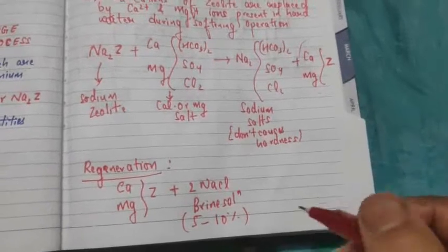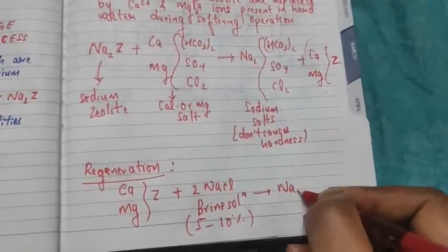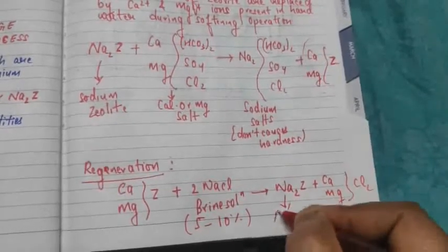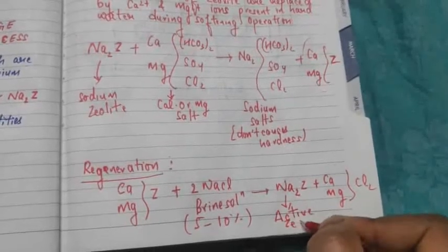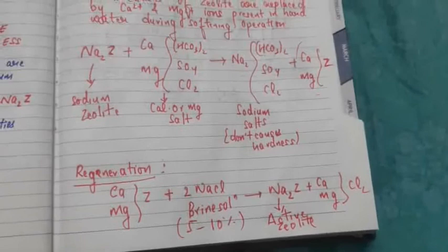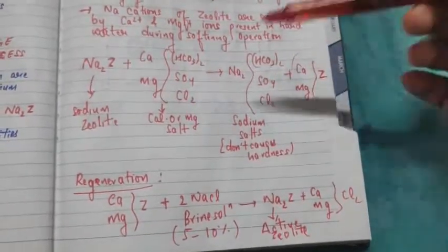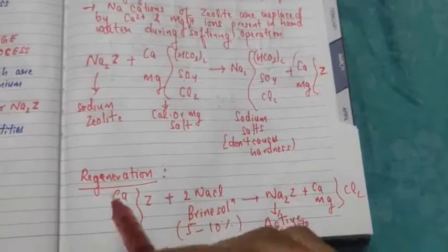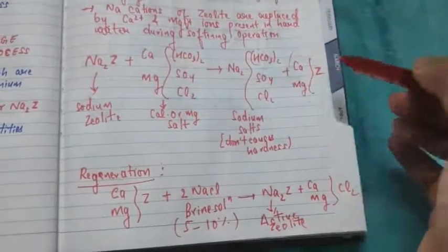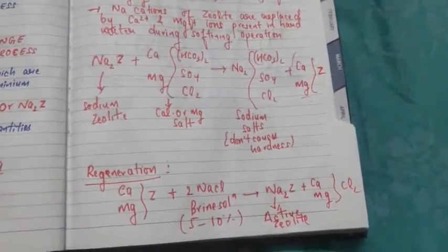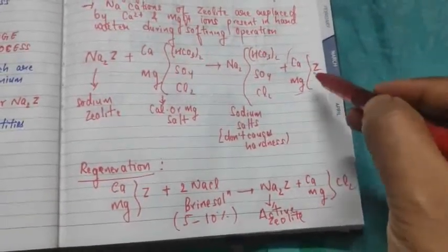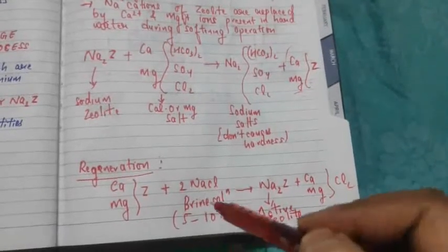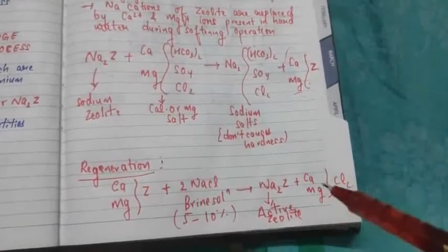On treating with 5–10% brine solution, the calcium and magnesium zeolites are converted back to Na₂Z — the active zeolite — so that the softening process can resume. This is the regeneration process.